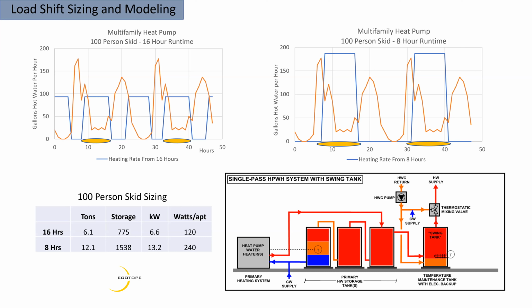If you size for 16 hours, it's 6 tons and 775 gallons of storage, with a peak draw of 6.6 kW, or 120 watts per apartment. That's the real value of central heat pump water heating: our load gets distributed across many units, so we can really knock down the peak draws when we go to central. That's the argument for going to central hot water: you get a lot of control over when you use this energy, and because of the storage, the loads are really small. This will be a key piece of the tool going forward.